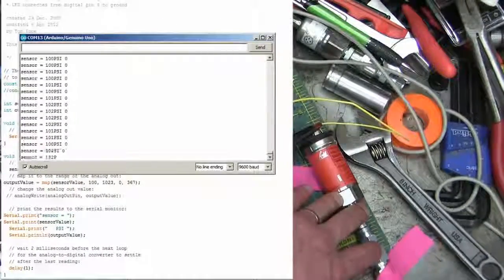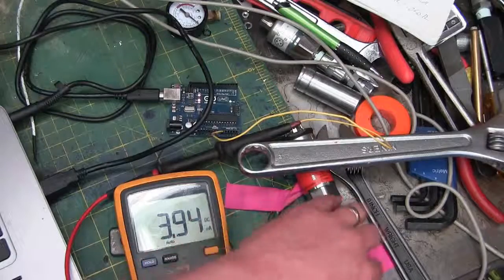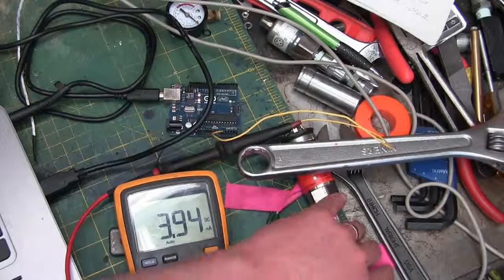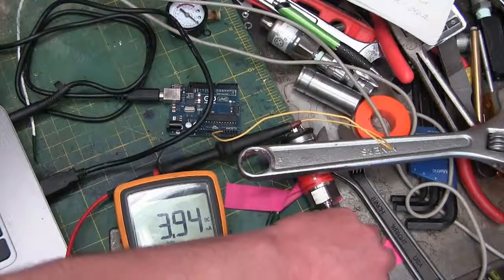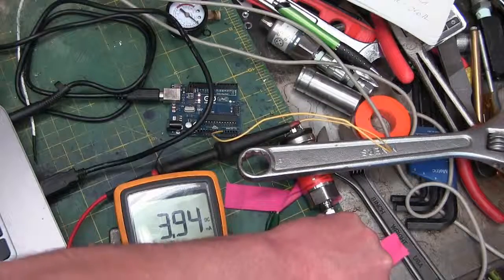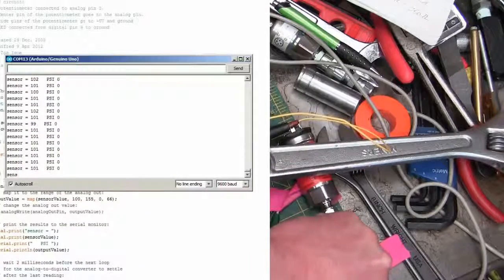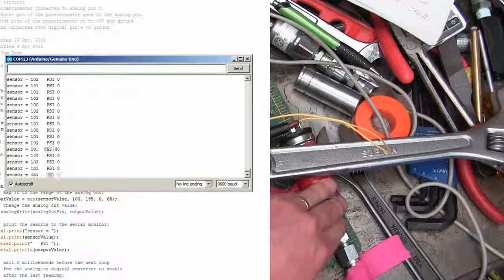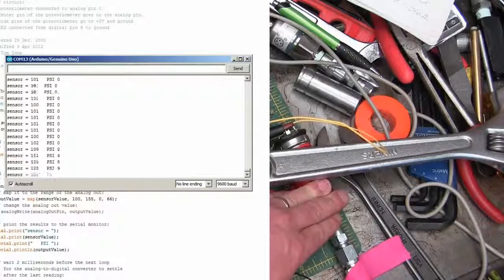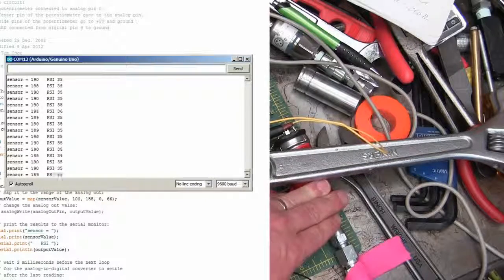So we've got 0 psi in the sensor now. We're going to put 110 psi in there and see what it pops up to. 190.